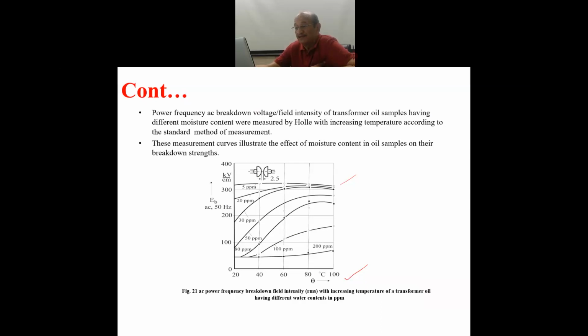But when the humidity content is increasing, well, over time it does happen, when the transformer is under rain and different weather conditions, that it has a humidity ingress property. Humidity is absorbed by the transformer. Howsoever you may try to prevent humidity from reaching the transformer, it does reach. So when it is of the order of 100 ppm and 200 ppm, the same breakdown strength of more than 300 kV per centimeter reduces to something like only 50 kV per centimeter. What a drastic reduction in breakdown strength. And then it is not desirable to continue with the oil under such conditions. They must do something to purify the oil.